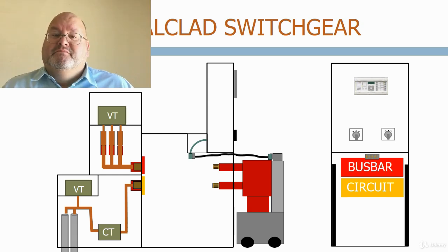The circuit and busbar shutters ensure that when the circuit breaker is withdrawn, the live busbars and cable connections behind them cannot be accessed. They are operated by mechanisms on the side of the circuit breaker enclosure. When the circuit breaker is pushed in by a fixed distance, the shutters open so the circuit breaker can engage with the live contacts. When the bus bars or cable connections are being maintained, the shutters can also be padlocked closed to provide a point of isolation and prevent the circuit breaker being pushed into the enclosure.